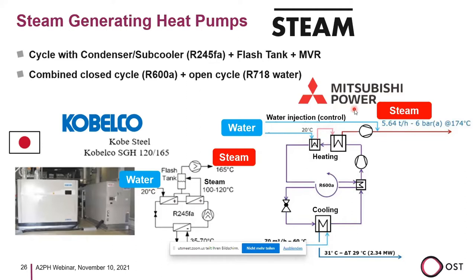Another system is Mitsubishi Power. It has a closed cycle heat pump with isobutane. It's of much larger capacity, actually in the megawatt scale. They also have the compression here and an open loop water recompression with water injection control.